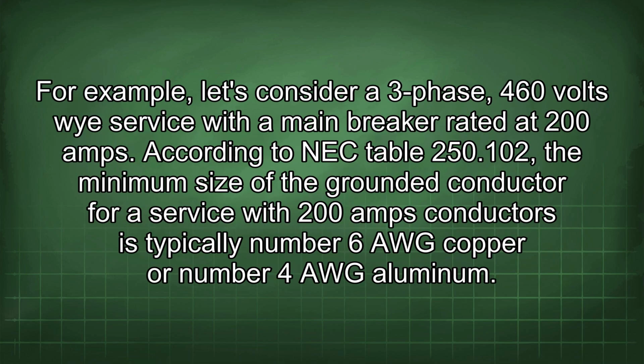For example, let's consider a three-phase 460 volts Y service with a main breaker rated at 200 amps. According to NEC Table 250.102, the minimum size of the grounded conductor for a service with 200 amps conductors is typically number 6 AWG copper or number 4 AWG aluminum.